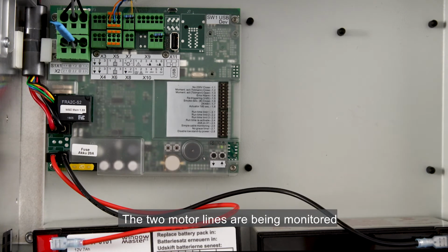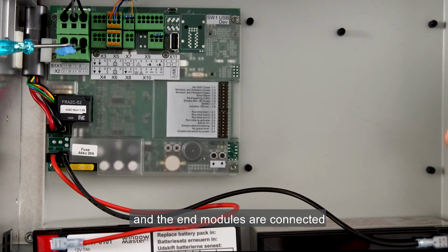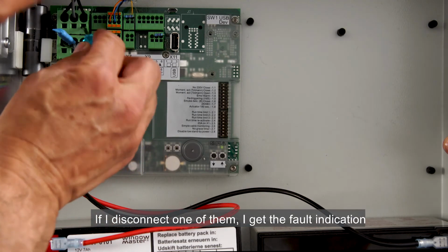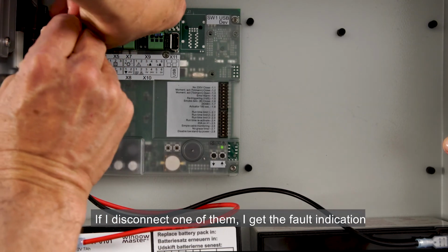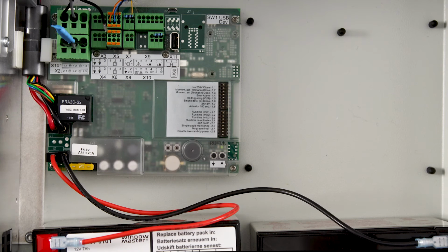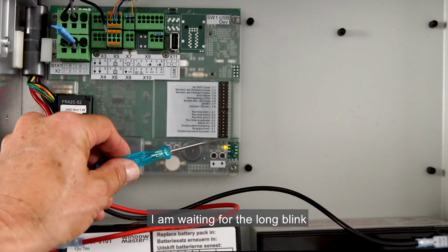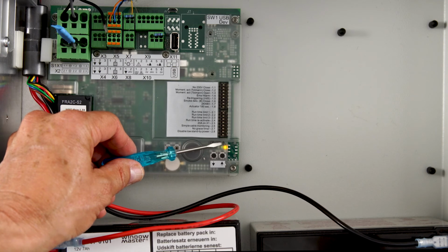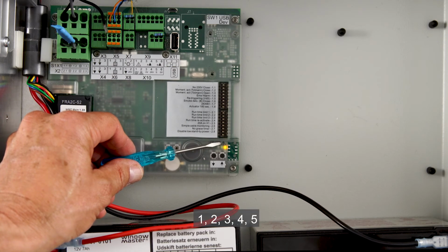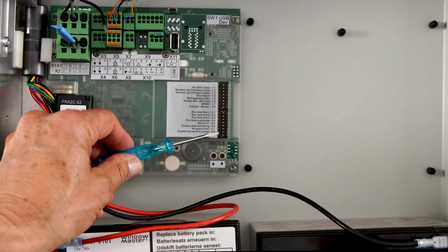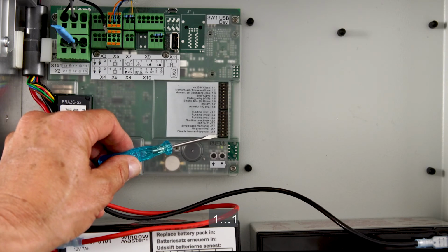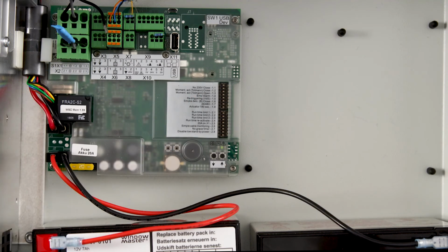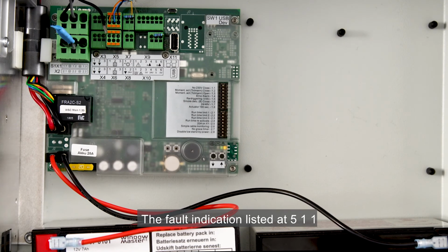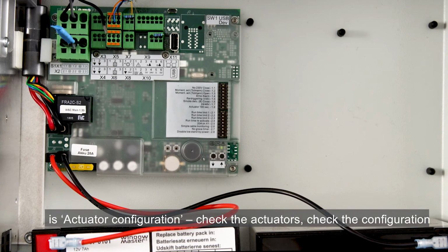The 2 motor lines are being monitored and the end modules are connected. If I disconnect one of them, I get the fault indication. I'm waiting for the long blink. 1, 2, 3, 4, 5. 1, 1. The fault indication listed at 5, 1, 1 is actuator configuration, check the actuators, check the configuration.